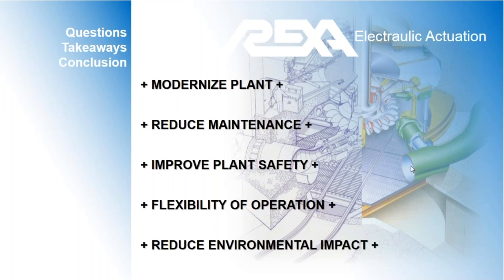For the last 2 years, we've gone into what we call load shaping. In high-demand periods of the day we offer more generation, and in off-peak periods we offer less generation, allowing the upper reservoir to recover. There's a schedule that's market responsive, and the way we do that is to program the control system with set points for the plant. You can see the possibilities here. Again, the needle drive in this case with the REXA has been very precise and extremely reliable.